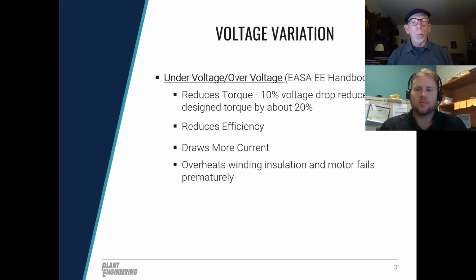So also, we talked earlier about voltage drop. Low voltage motors may, just for example, be rated at 460 volt, but grid voltage coming in from the utility may be 480 volt. So that's what we talked about, voltage drop in the distribution line coming from the nearest substation or distribution transformer.